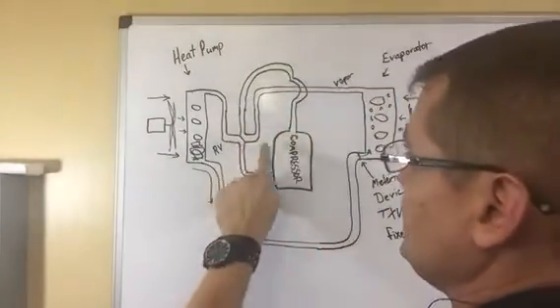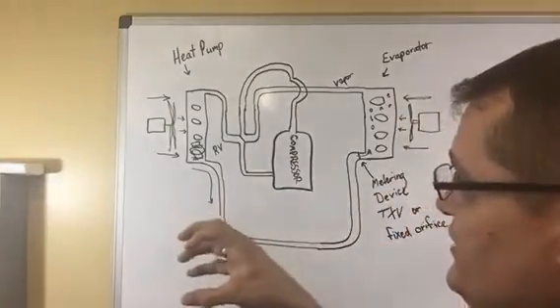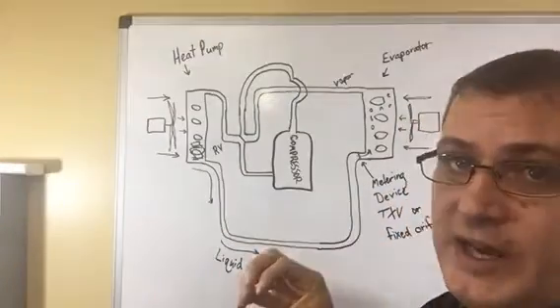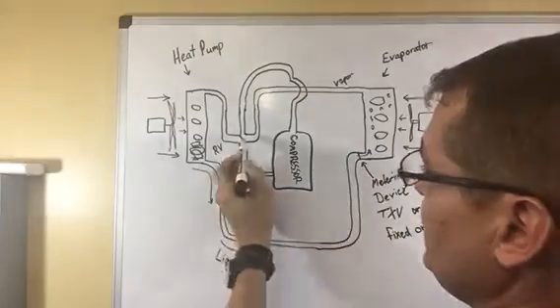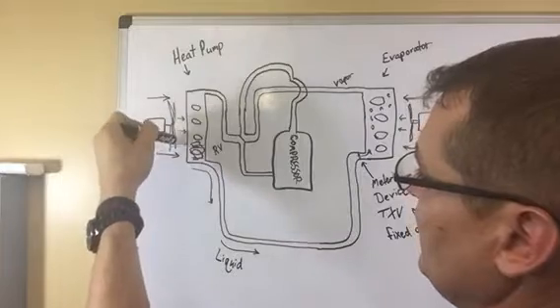This is how a reversing valve works. It just has a solenoid that shifts back and forth. So in cooling mode, the solenoid is shifted like this. So your hot gas comes out and feeds your outdoor coil.